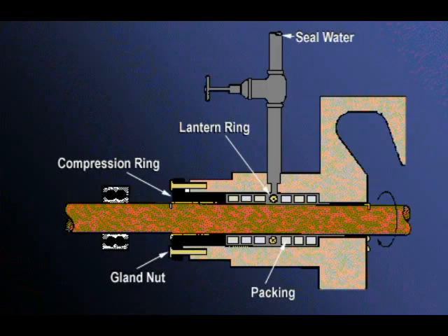After removing the top rings of packing, the lantern ring must be removed. This may be fished out with a heavy piece of wire, coat hanger, or welding rod. Some lantern rings have a threaded hole in which a 6 mm quarter-inch bolt can be inserted. If the pump has been in service for a while, clean around the shaft and stuffing box to remove the lantern ring. A tap with a wooden dowel may be necessary to loosen it.